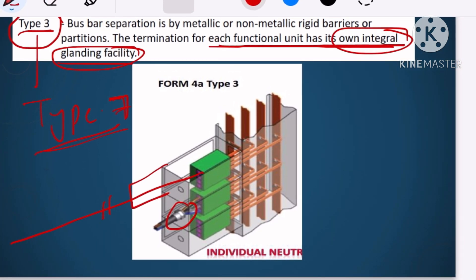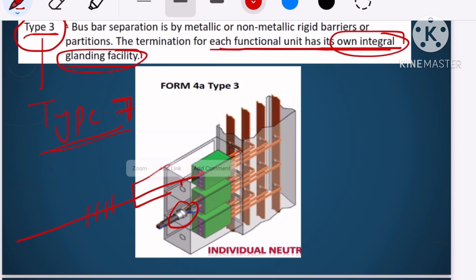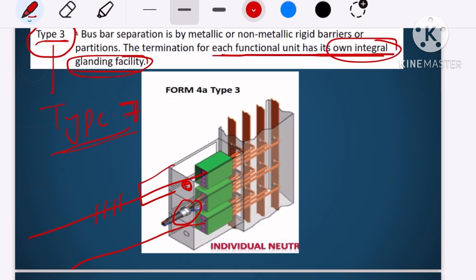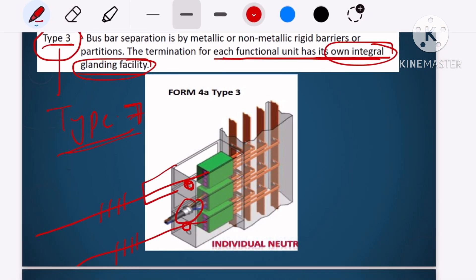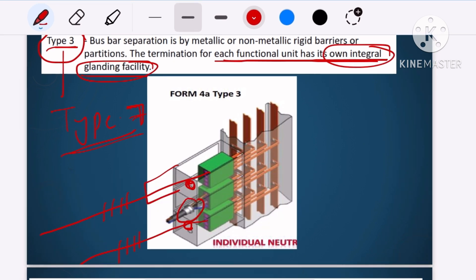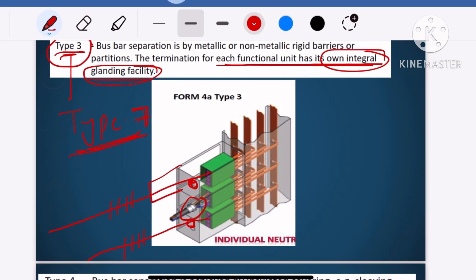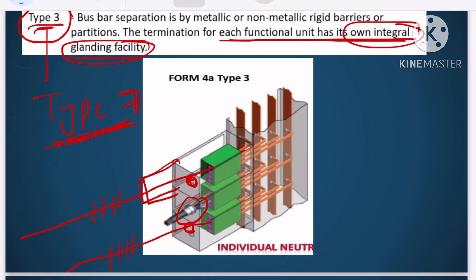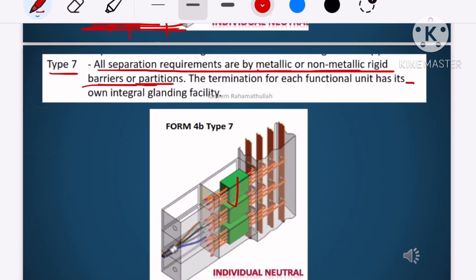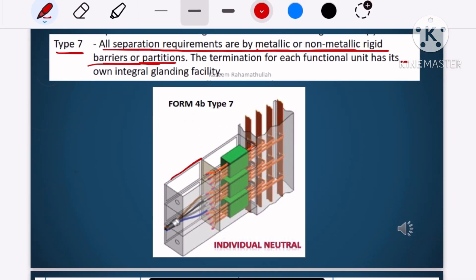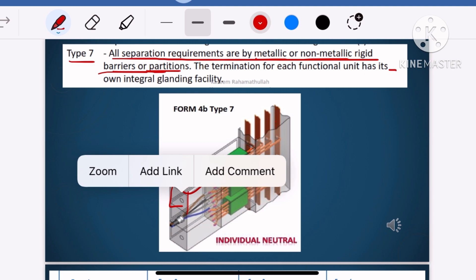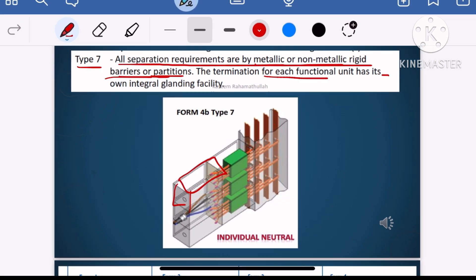In type 7, the external cable — R, Y, B, and neutral — will come, but the glanding of the cable will be at the functional unit itself, not at a common glanding plate. The difference between type 7 and type 3 is that in type 3 there is no separate compartment for termination, whereas in type 7 there is a separate compartment for termination. But like type 3, type 7 has a glanding facility near each functional unit.